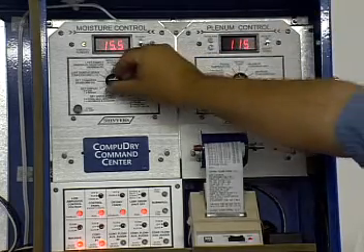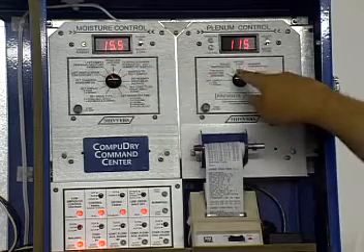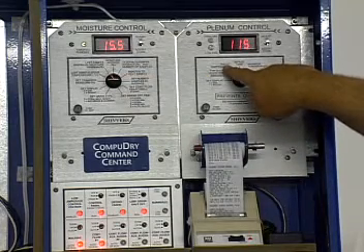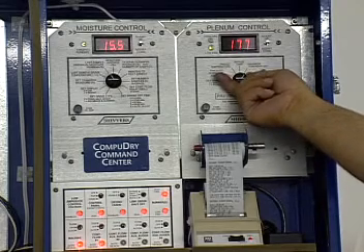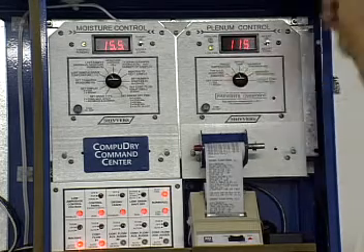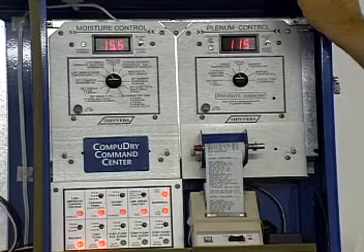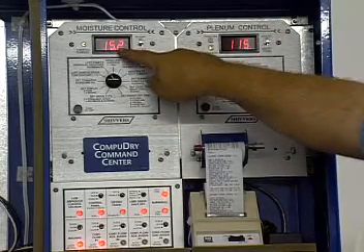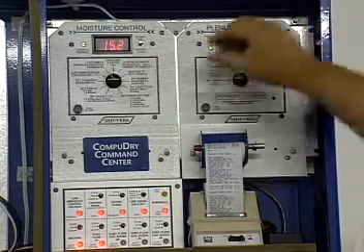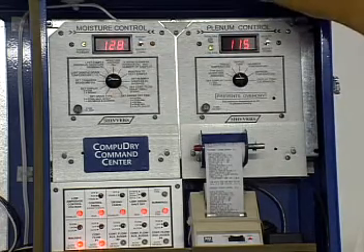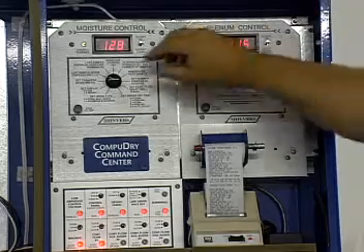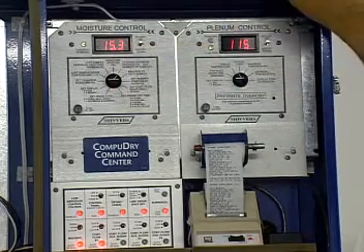Now, if we start getting into wet corn over here, then the computer will go over and raise target temperature. Target temperature will go up as high as 177 degrees. But right now the computer's saying, I don't need to go up that high. We're fine because my moisture is less than where I have it set. This is my transfer. That's the actual temperature of that corn, 128 degrees. We've just made the second transfer.